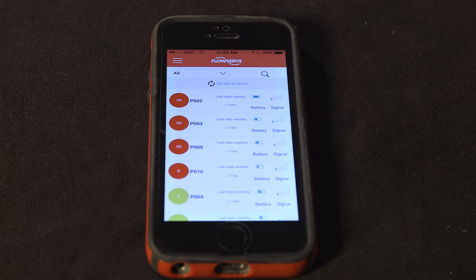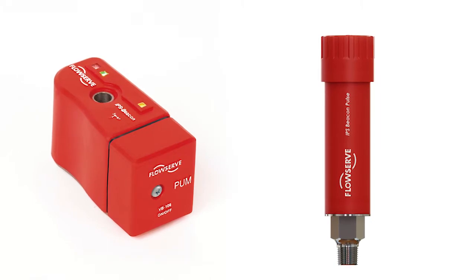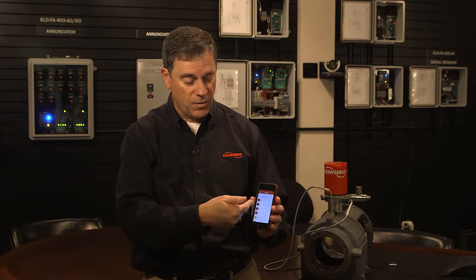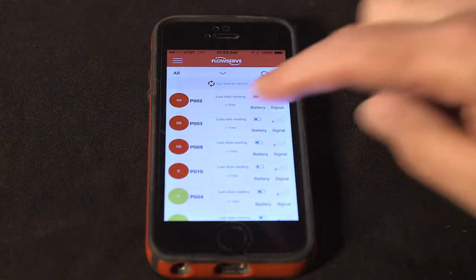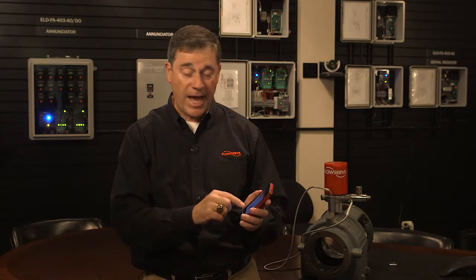When you're in range of either the IPS Beacon or the IPS Beacon Pulse, it communicates with them every two seconds — either the Beacon or the Beacon Pulse is putting out its status and a range of information. If it's blinking red, all the red is brought to the top for each device that you're connected to and paired with, and you can drill down. You can click in and adjust parameters, thresholds, and see what your configuration is. If there's a last alarm that happened and it's blinking red, you can see when that last alarm happened.